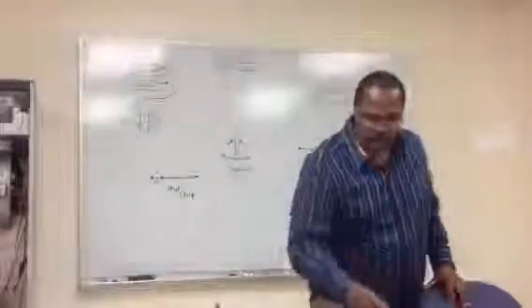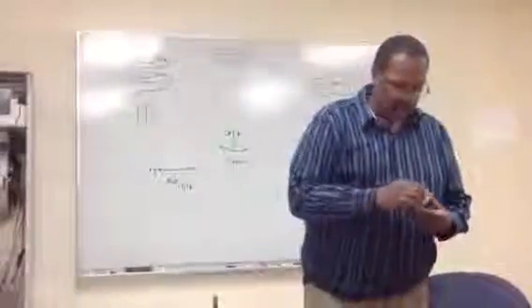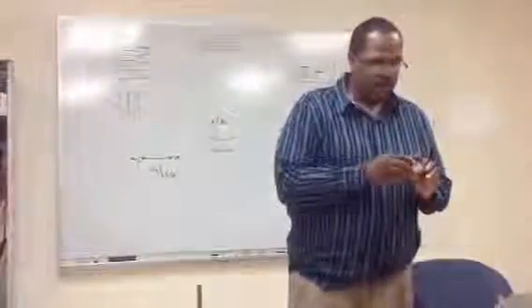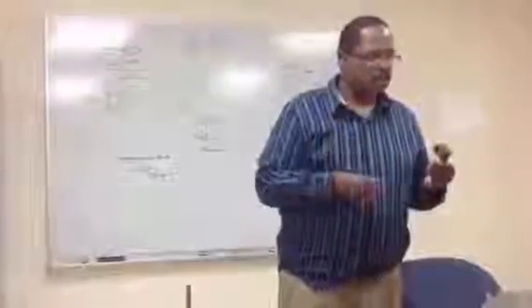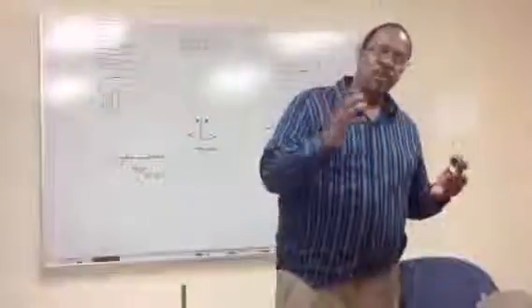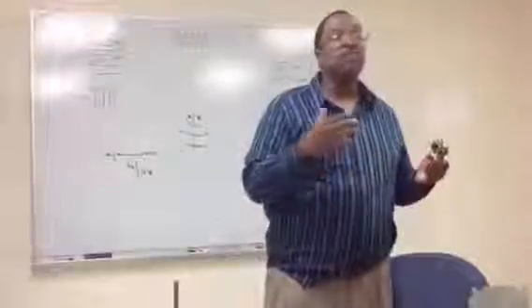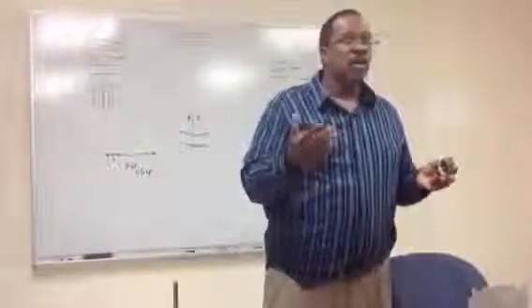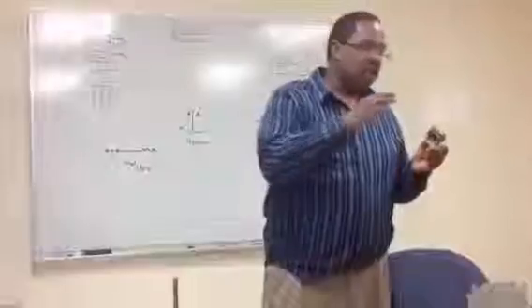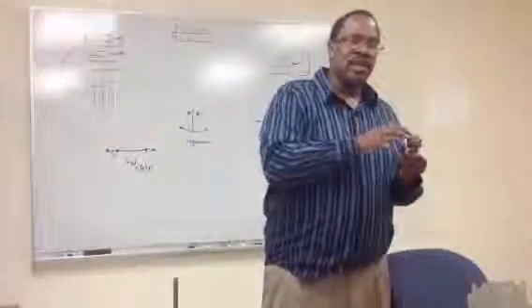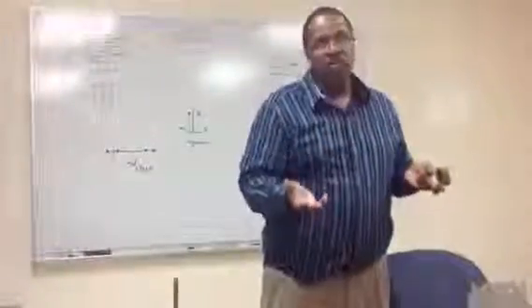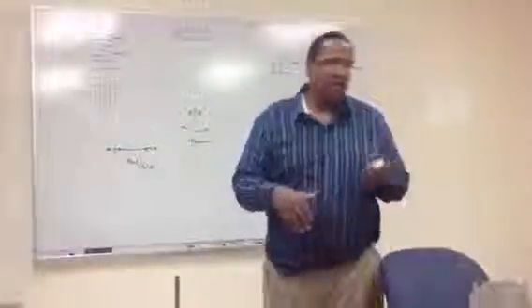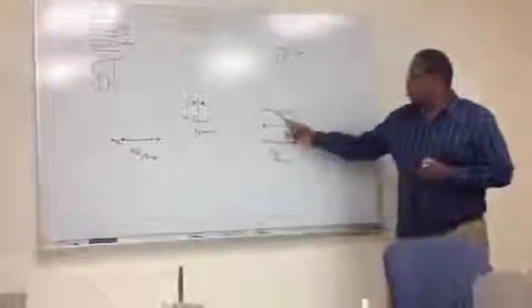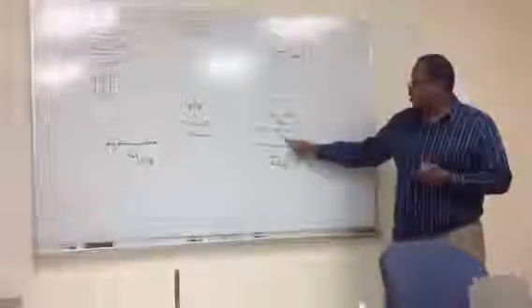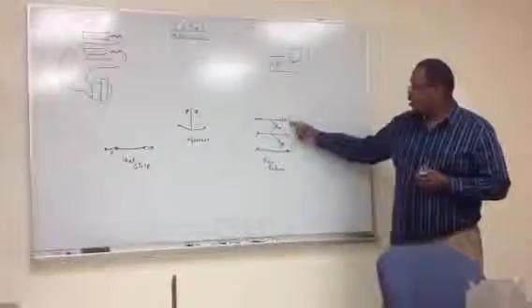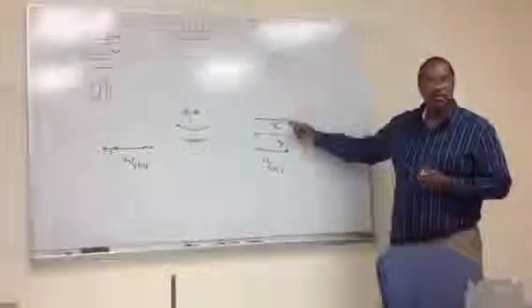Now, here are some fan relays. We're just going to discuss some of them, but there are many of them out there, and they all seem to have the same purpose. They're all going to have some normally closed switches as well as normally open switches on them. Normally closed and normally open means in their off position, when they're not being energized, they're going to be either normally closed or normally open. Some will have little markings like this. That means normally closed. Some will have markings like this. That means normally open.